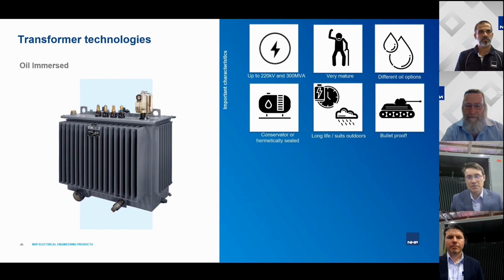The other important factor is that oil transformers are very resilient to overvoltages, because if there is a network overvoltage, for example, it will result in a momentary breakdown in the oil. However, the oil dielectric properties will restore very quickly, because it will naturally mix up, and all that carbon will go away from that point of fault. So essentially, oil transformers are self-healing after overvoltage events, which won't be the case, by the way, in a cast resin transformer. So that's why we're saying it's pretty bulletproof.